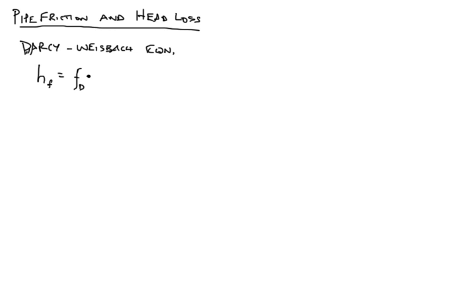Times the length of your pipe—so if you're pumping it a thousand meters that would go there—and then the internal diameter of your pipe. Back to the Darcy friction factor, that also has to do with the roughness of the pipe. If you have a very smooth pipe then you would get a lower friction factor. Times the average velocity of the fluid squared.